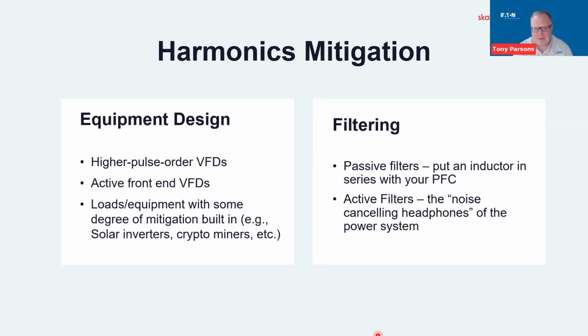But if we can't get rid of the harmonics with equipment design, maybe we can get rid of them with filtering. There are passive filters. We'll talk a little bit more about power factor correction in a few moments, but kind of giving you a preview. If you put capacitors in your system to help correct your power factor, you can also put an inductor in series with it to tune it and essentially make it into a harmonic filter. Typically with that, you're targeting one harmonic, that may be your most problematic. But there are such things as active filters as well. And I call that the noise canceling headphone of the power system.